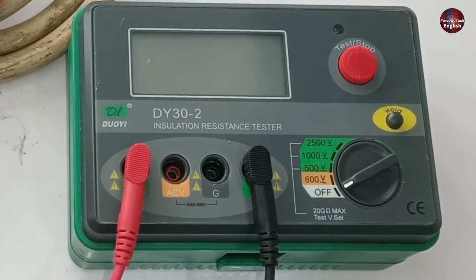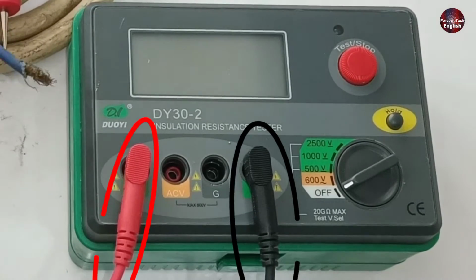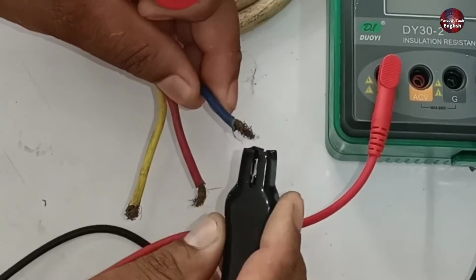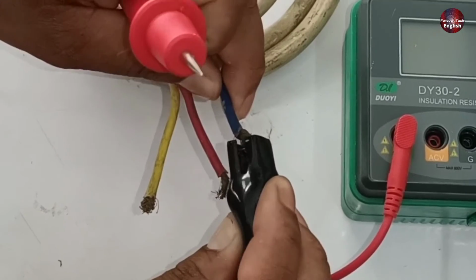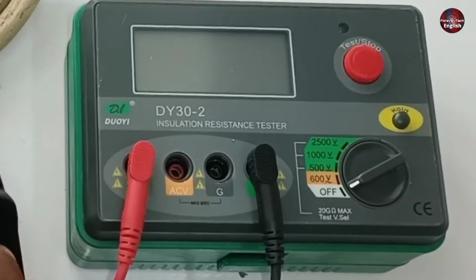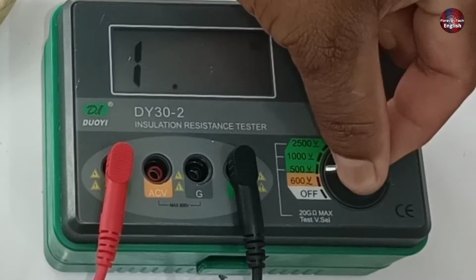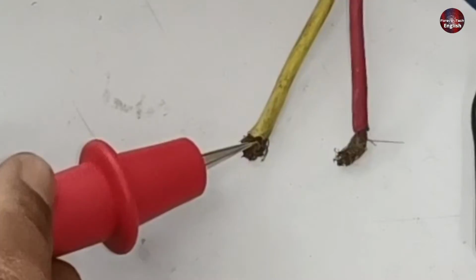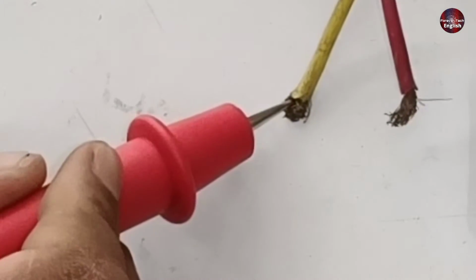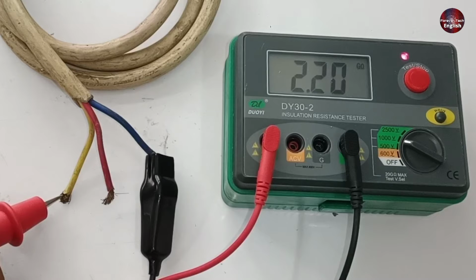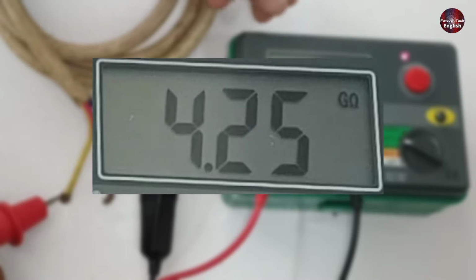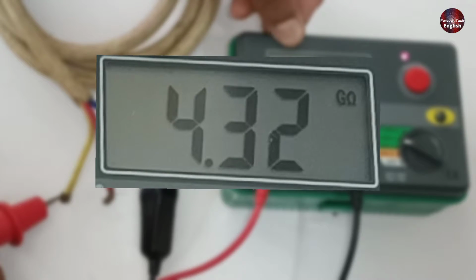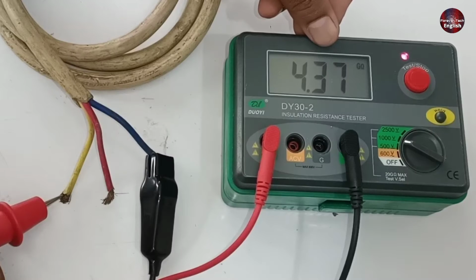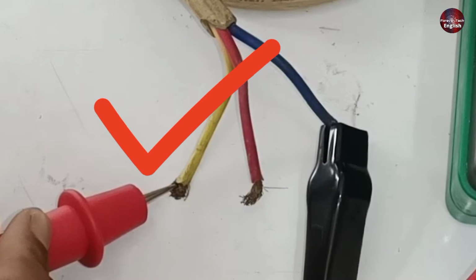I have attached the probe leads with the megger, with the line and earth terminals. Now I am attaching the alligator clip with the blue wire. Now I will rotate the selector switch and set it to 1000 DC volts. I have attached the second probe with the yellow wire and pressed the start button. The megger displays 4.32 gigaohms, and the resistance value is quite large. Now, this means this wire is good.